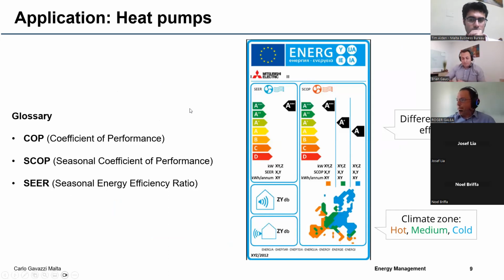So, linking with what Mark started, he mentioned net zero. An important target when you look into net zero is heat pumps. Now, from the ECO directive of September 2017, manufacturers of heat pumps are enforced to show not only the coefficient of performance, but the seasonal coefficient of performance, because in Europe, for example, we have different performance because of the different climates. So now they are enforced to change how they show the labeling, like we have on our fridges, microwaves, etc. To achieve a good rating in this new labeling system, they need to change to a synchronous motor. Roger mentioned asynchronous and synchronous; they need to go for a permanent magnet motor.